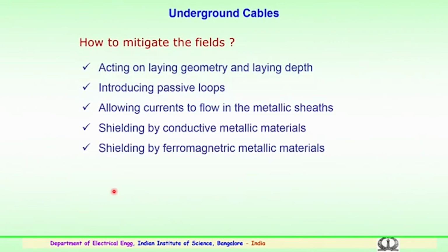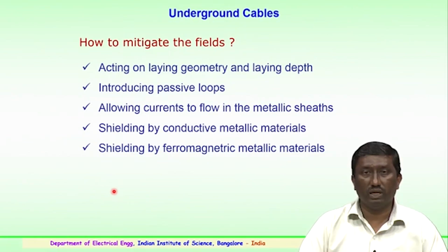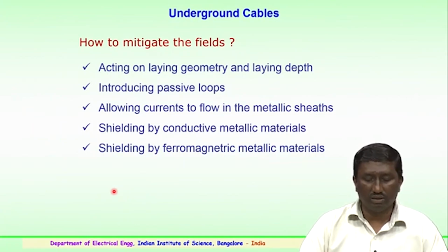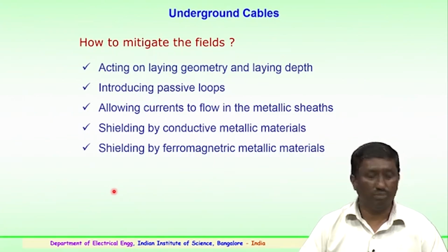How to mitigate the fields, particularly for underground cables? For the overhead conductors we have seen. For the underground cabling, again it depends on the laying geometry of the cable, how it is laid, and what is the depth of the cable trench adopted for the voltage and the dimension of the cable. So, here also introducing passive loops could help in reducing the magnetic fields, also allowing currents to flow in the metallic sheath on the cables. Then shielding by conductive metallic materials will further help in reducing the magnetic fields of the underground cables, and shielding by ferromagnetic metallic materials will also help to reduce the fields.